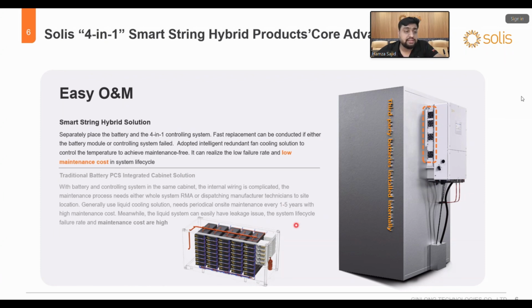The system life cycle failure rates and maintenance costs are high. But in Solis, it is a different thing. We have the fans outside the inverter. You don't need to jump into the inverters and check all the things, because both of the things are not installed inside the inverter. So you can easily install the inverter outside the box of the battery, and it can easily work for you guys.